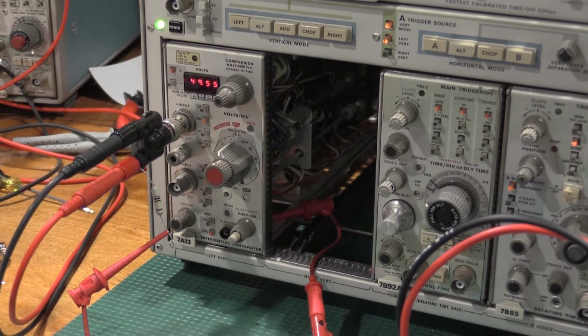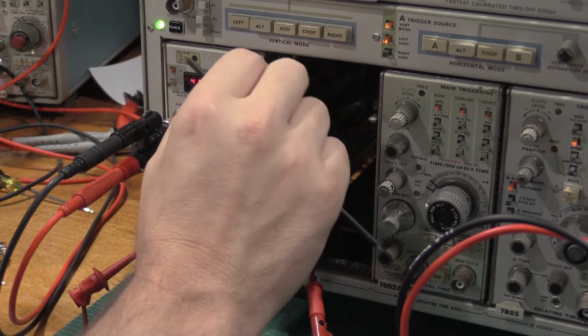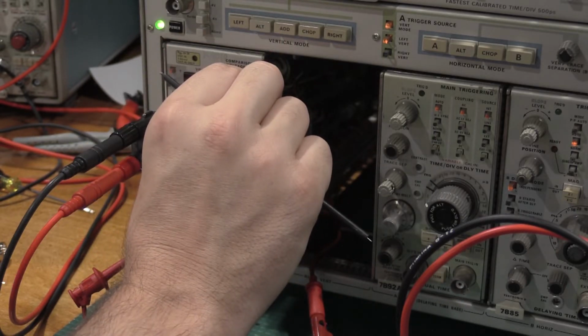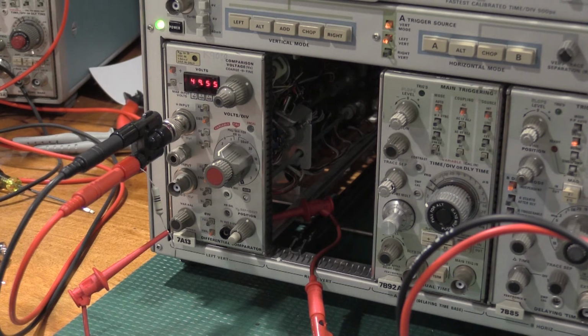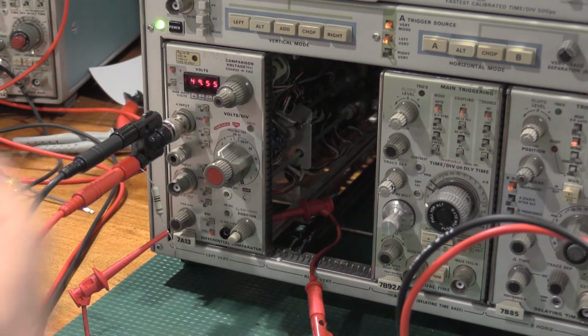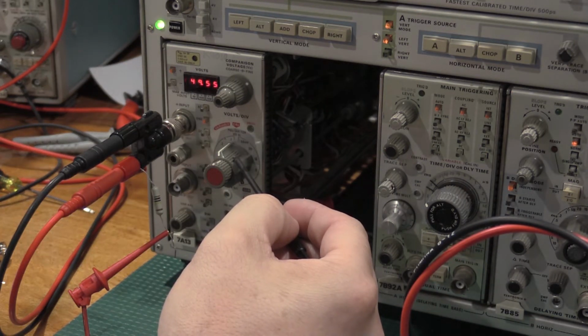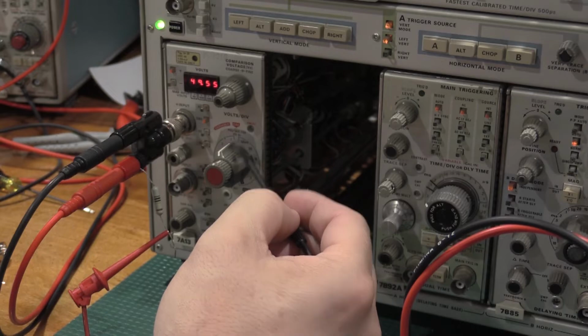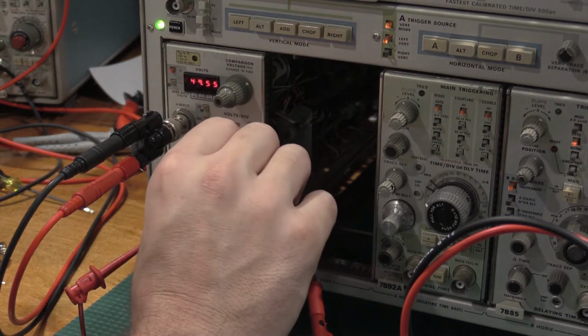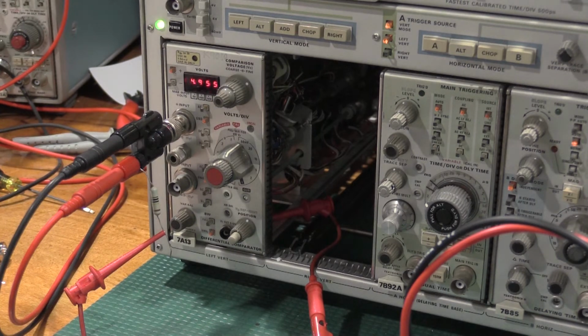And I'm at 4.5001 and we're kind of jumping, so back it off just a little bit. There we go. Come back a touch. All right, there we go. So now I need to take this and adjust this for 50 millivolts. So we're going to come down into the 1X attenuator, and we want to make sure the reading on the meter is within 50 millivolts for the 1X attenuator.